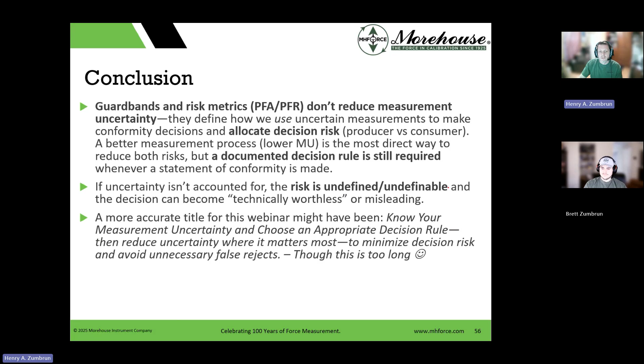So expanded uncertainty should include all significant contributors. We put that slide in. Guard band choice: tighter guard bands narrow the acceptance interval, so they lower the PFA but typically raise the PFR. So you have that trade-off. More good items fall outside acceptance. Higher TUR and measurement capability index generally reduce both false accept and false reject probabilities for a fixed decision rule. Lower MU effectively makes decisions more reliable, with less overlap near limits. And choosing better equipment plus better calibration reduces decision risk and avoids unnecessary guard band fallout.